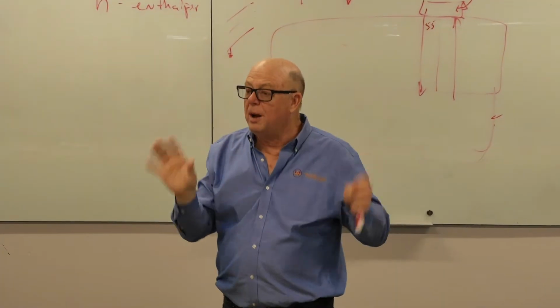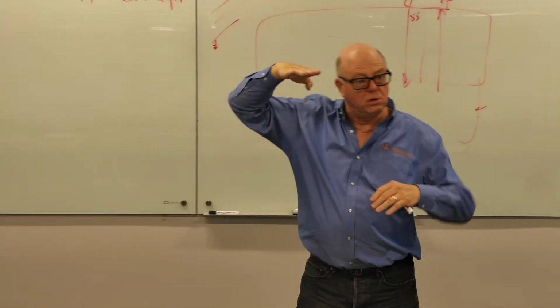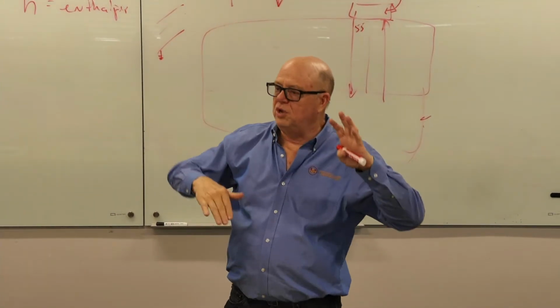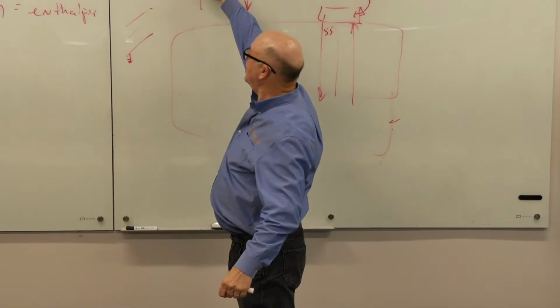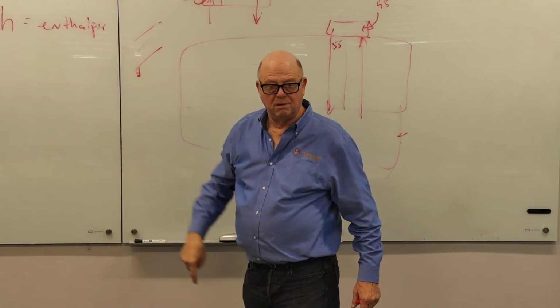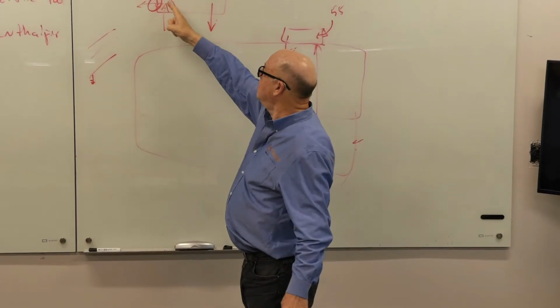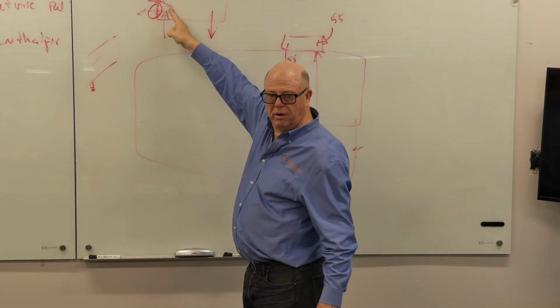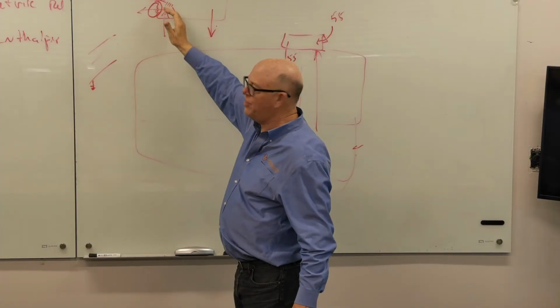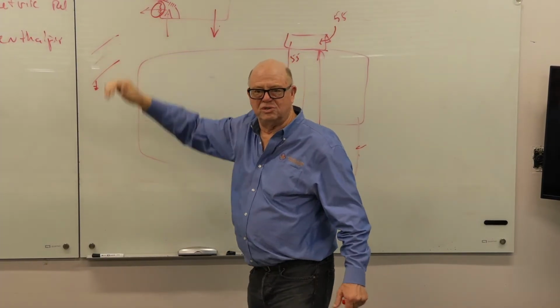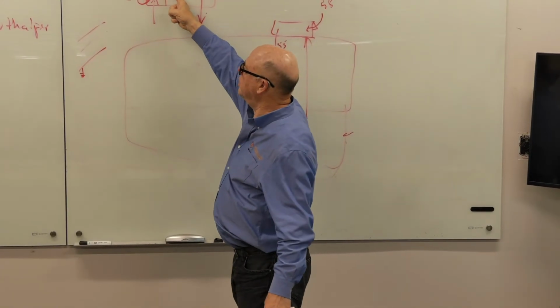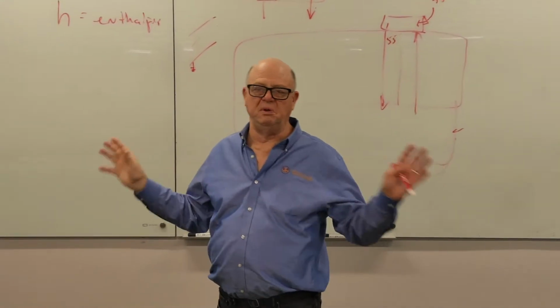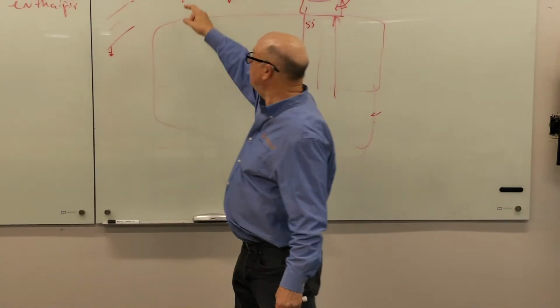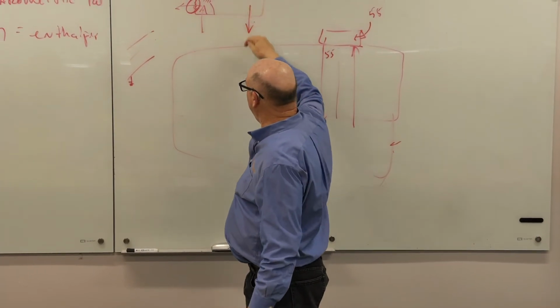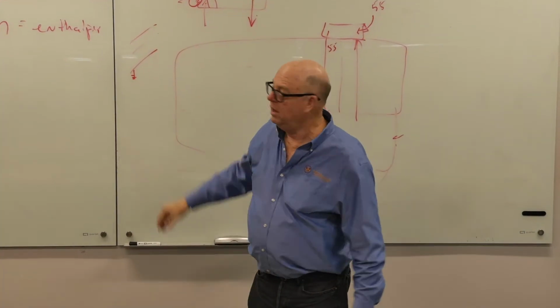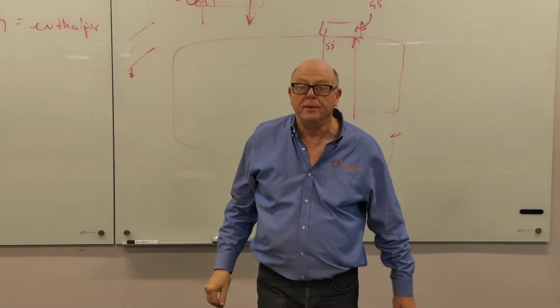So if you actually set the thing up well at startup, you could sort of equate the pressure that the return damper would go open with this. And if you did that, this damper becomes kind of unimportant, because what's the easiest path to escape? It's the shortest one, right? Now you'd have a damper here, but it didn't have to be low leak, it didn't have to be anything exciting, because if the return's coming up here, the pressure in the building will just push it out of there. And this little damper shutting is just help. Okay?